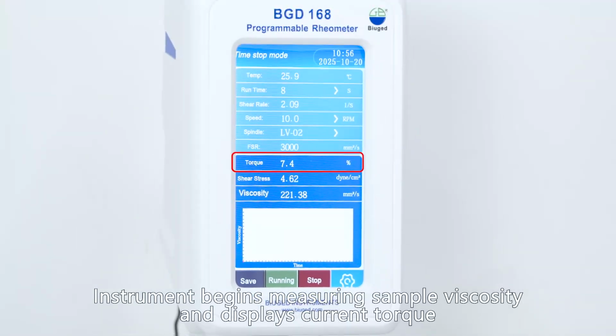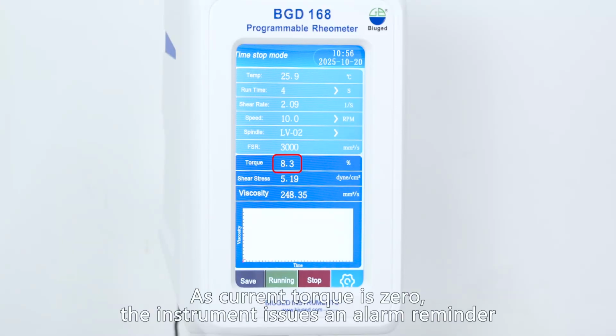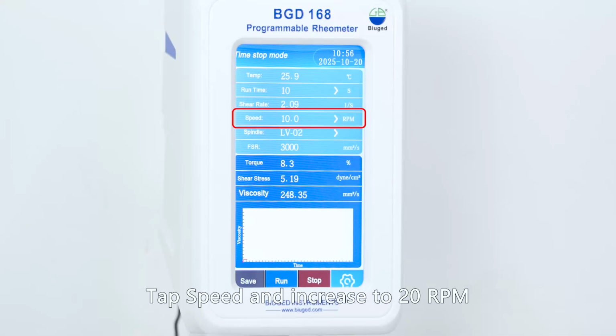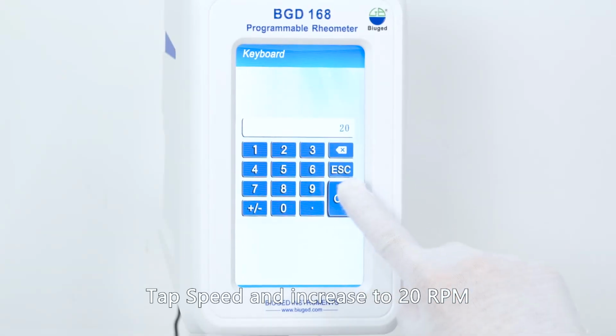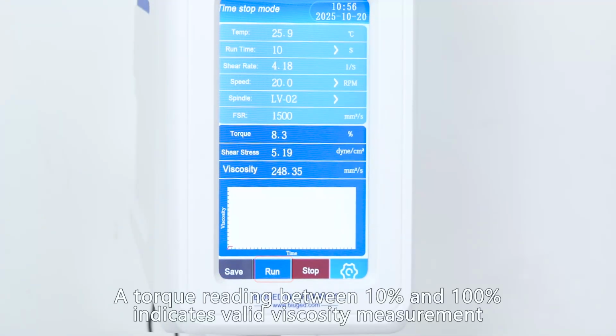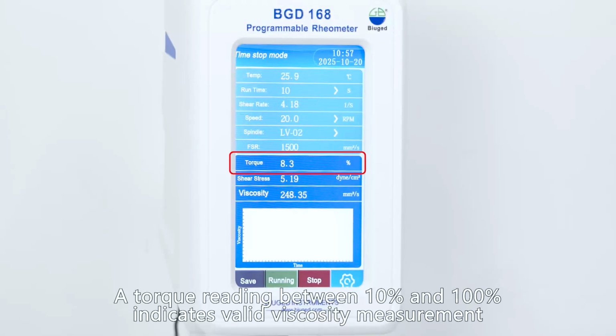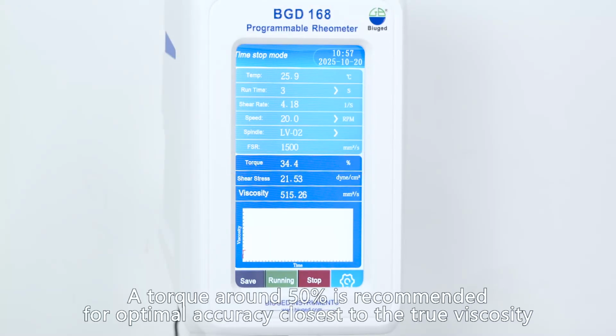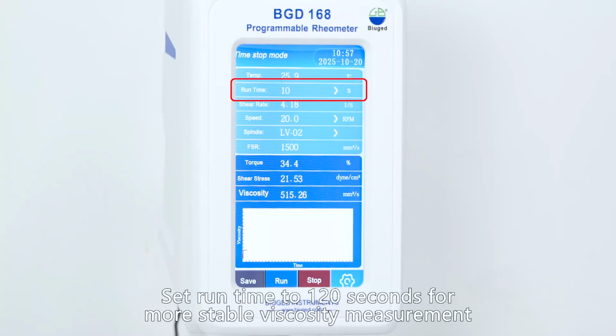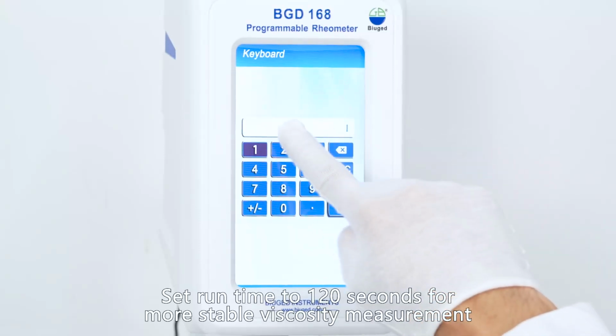Instrument begins measuring sample viscosity and displays current torque. Since the current torque is below 10%, the instrument will issue an alarm reminder. Tap Speed and increase to 20 revolutions per minute. Tap Run. A torque reading between 10% and 100% indicates valid viscosity measurement. A torque around 50% is recommended for optimal accuracy closest to the true viscosity. Set run time to 120 seconds for more stable viscosity measurement.